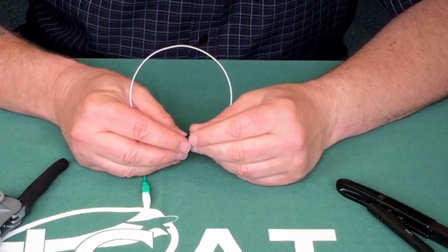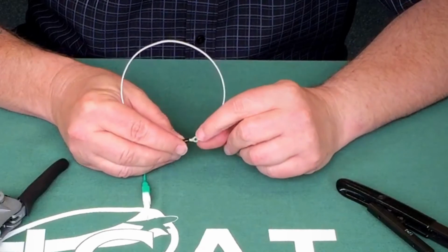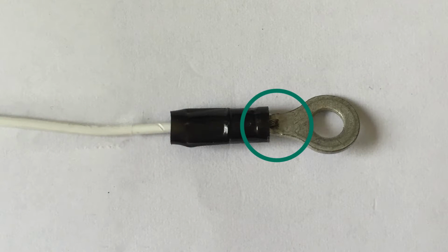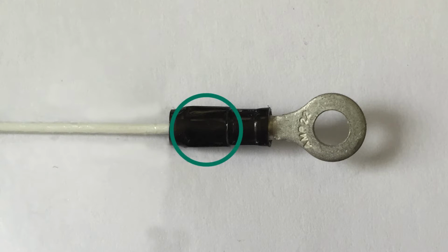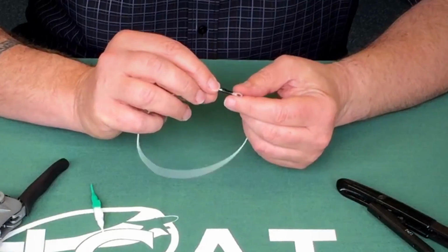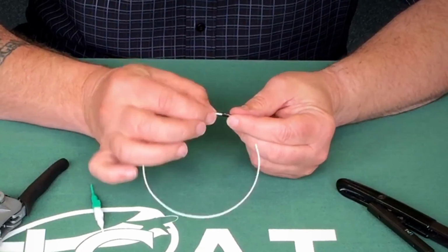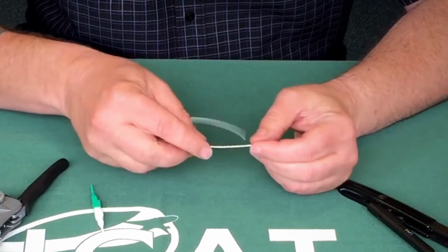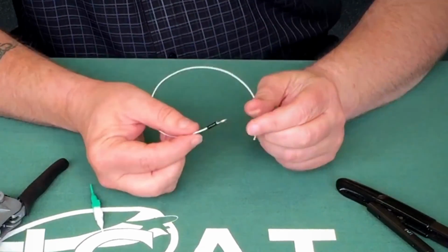And the thing I'm looking for here is that I can see the conductor protruding through the barrel, so it's correctly fitted in. And if you have a magnifying glass, you can have a look and there should be a dot code stamped on the back of the crimp. Well, now we've completed the crimp, we can move on and connect them up to the appropriate tag boards.